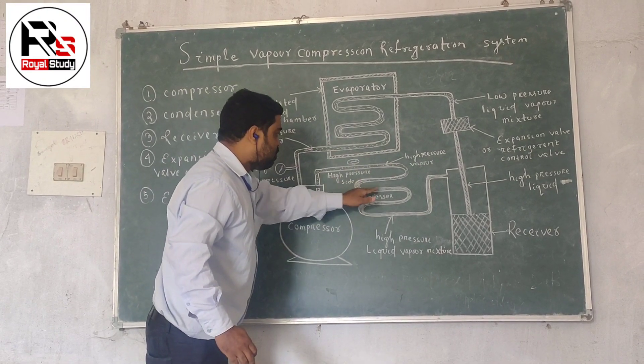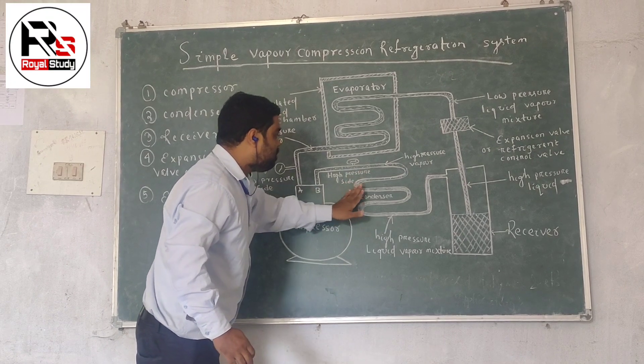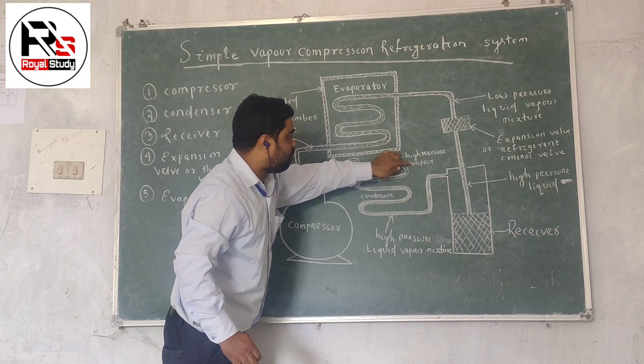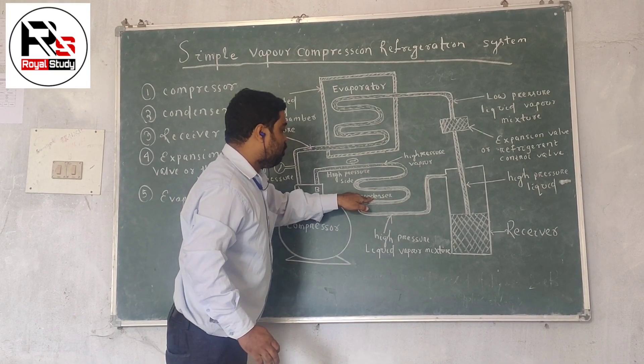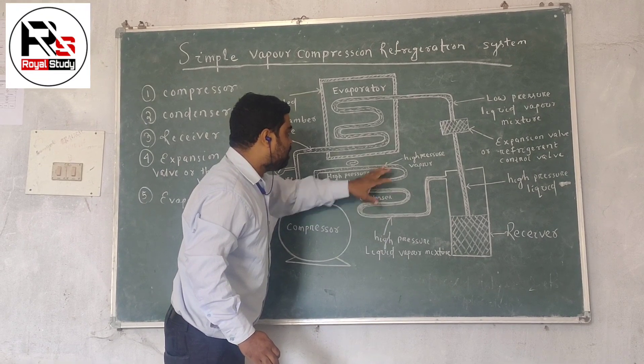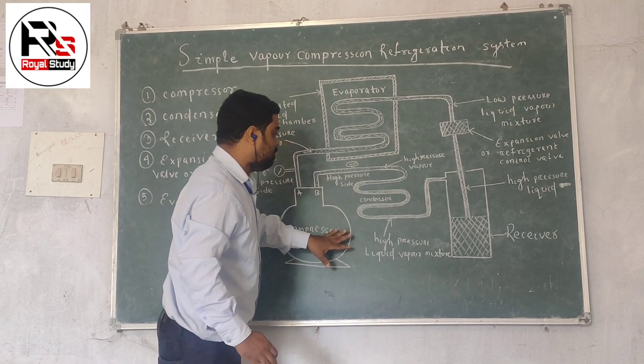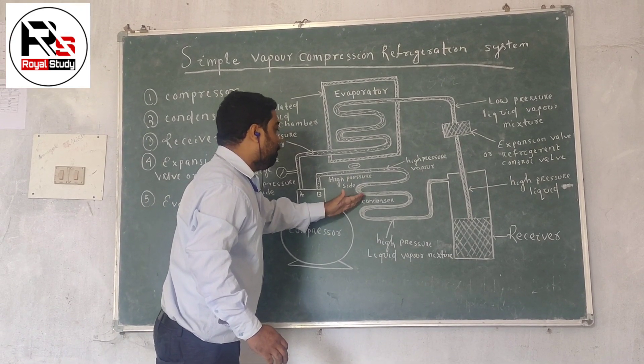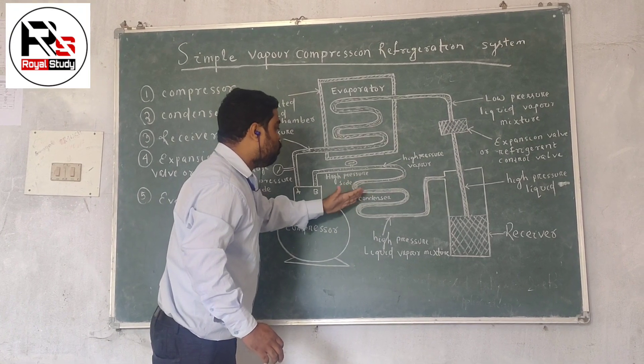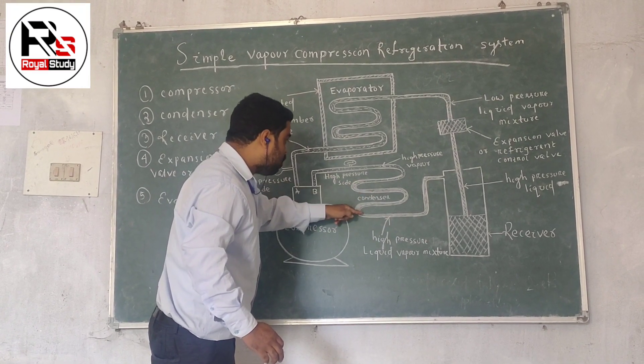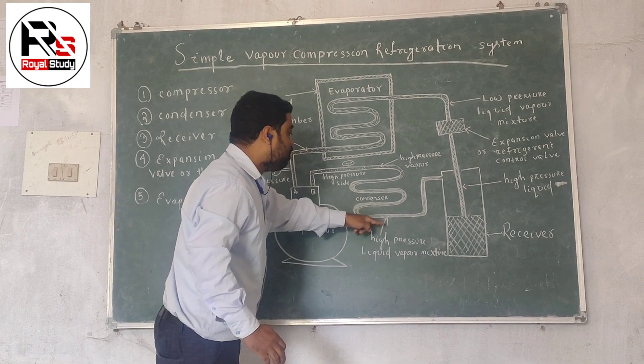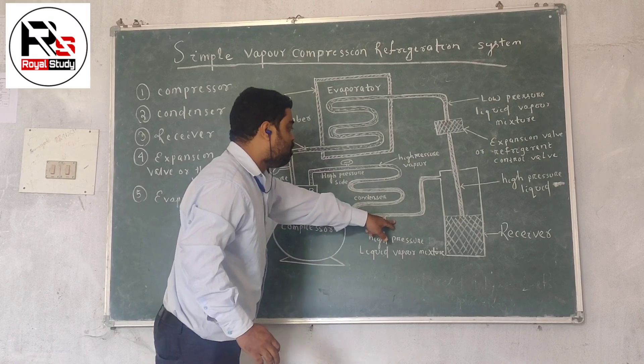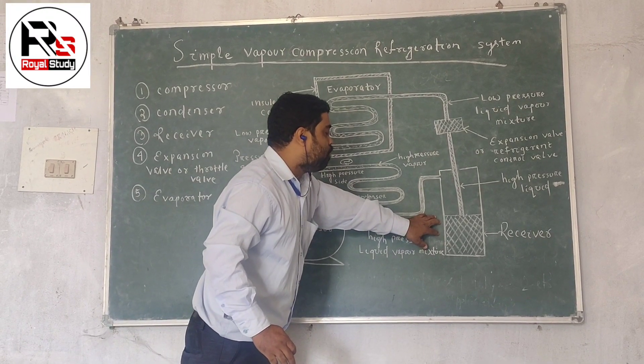The condenser is where the high pressure refrigerant is condensed. After the high pressure vapor comes to the condenser, the condenser condenses the high pressure vapor. Then it gives off latent heat to the surrounding medium — that is, air or water. After condensation, the liquid-vapor mixture at high pressure is stored into a receiver.